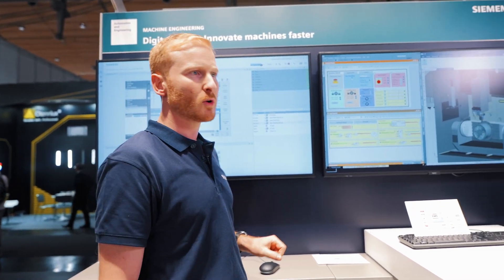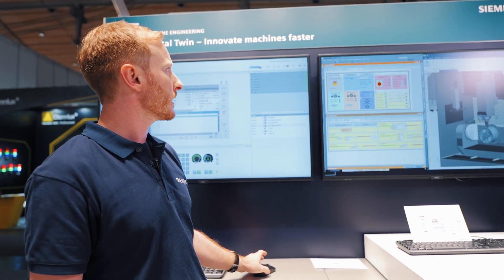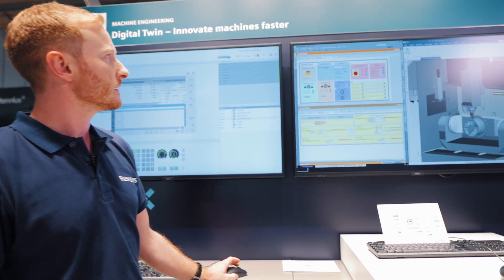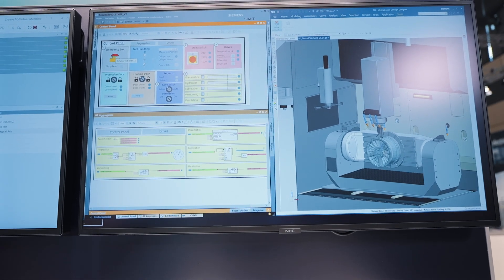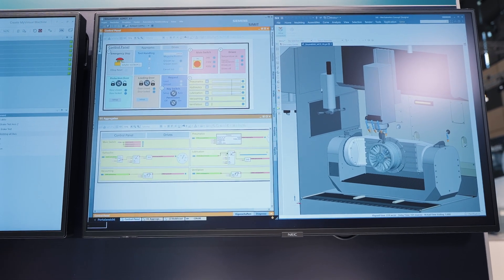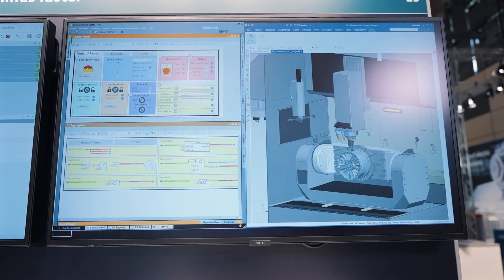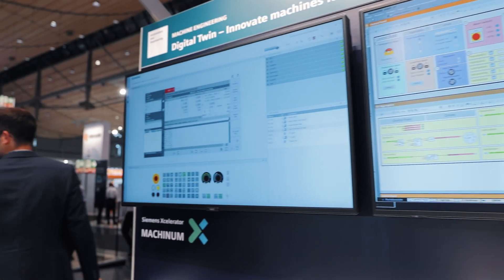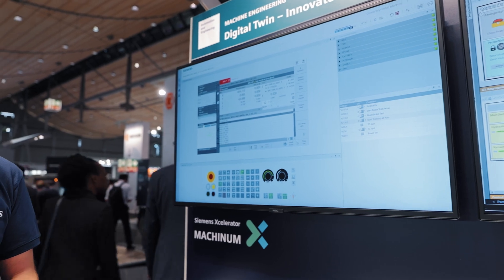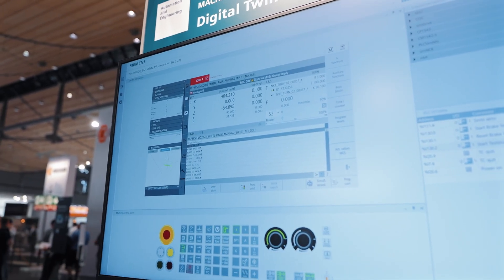Moreover, it is possible to simulate errors. This means a user can try out what happens when the emergency stop is pushed. I would like to demonstrate this — I am pressing the emergency stop. We see that the machine is at a standstill. The appropriate notification is sent to our control system, so that we can be sure the program logic is working.